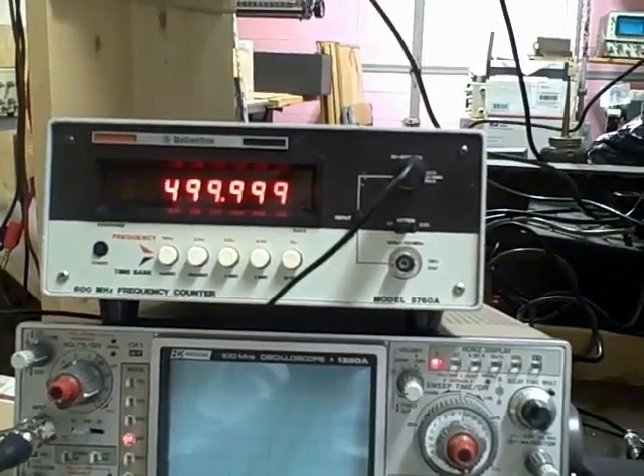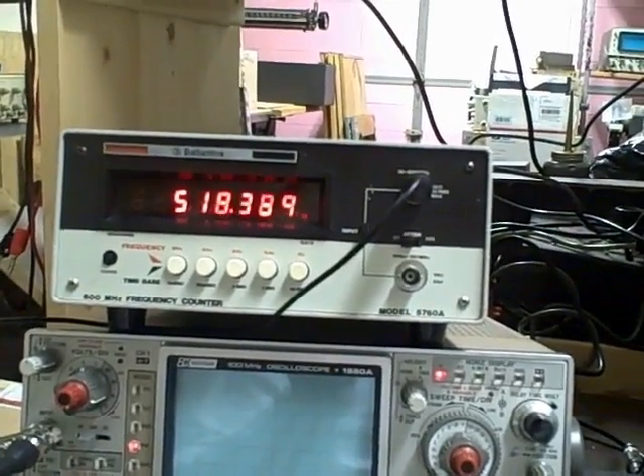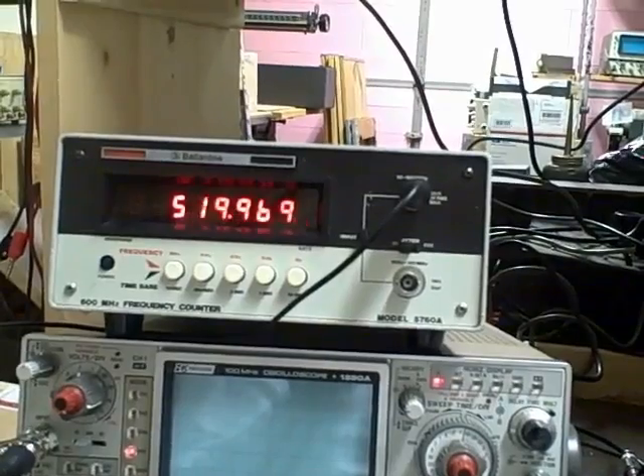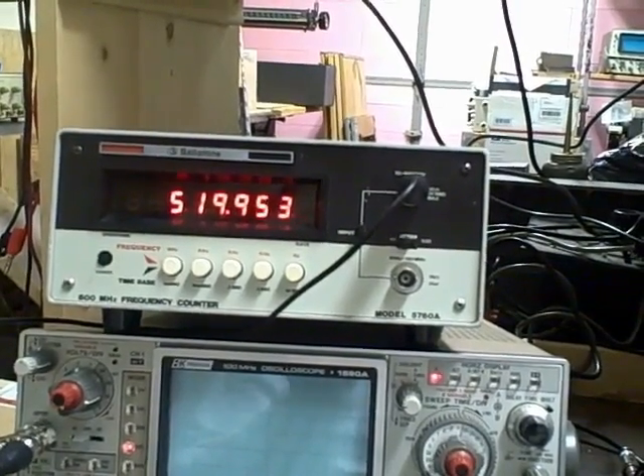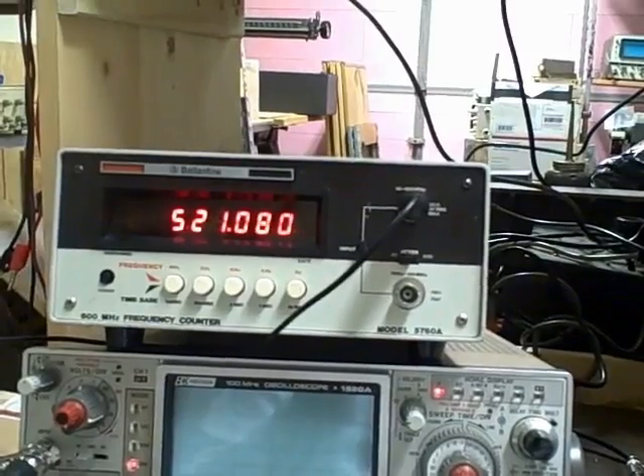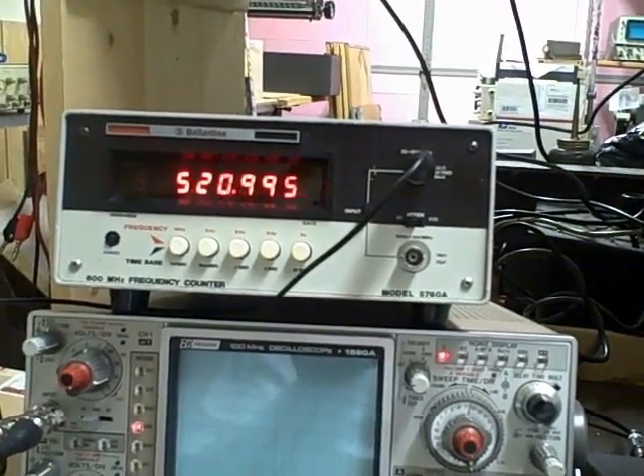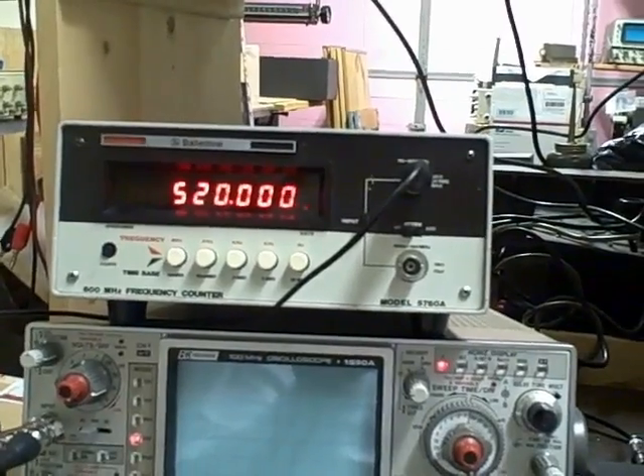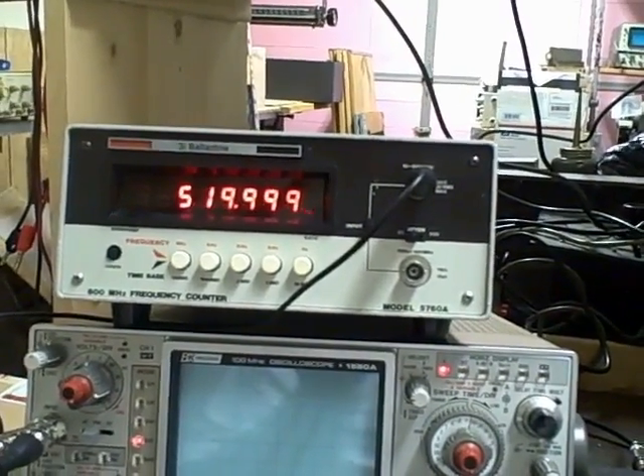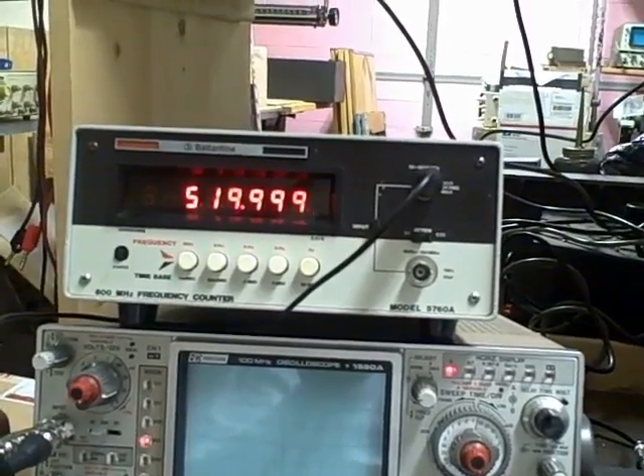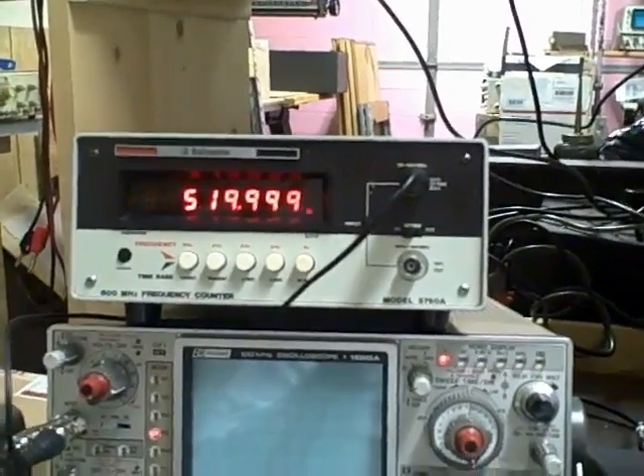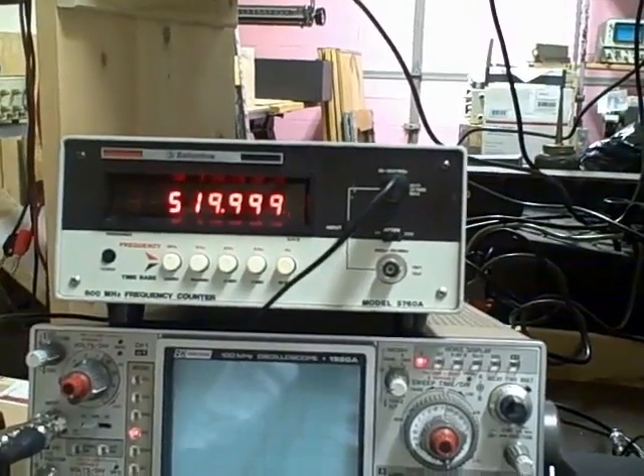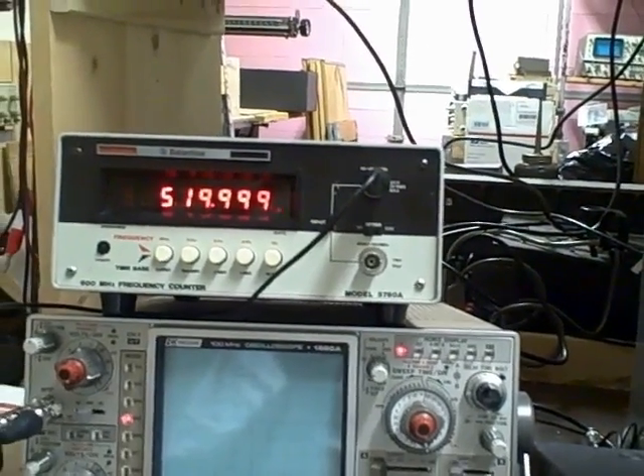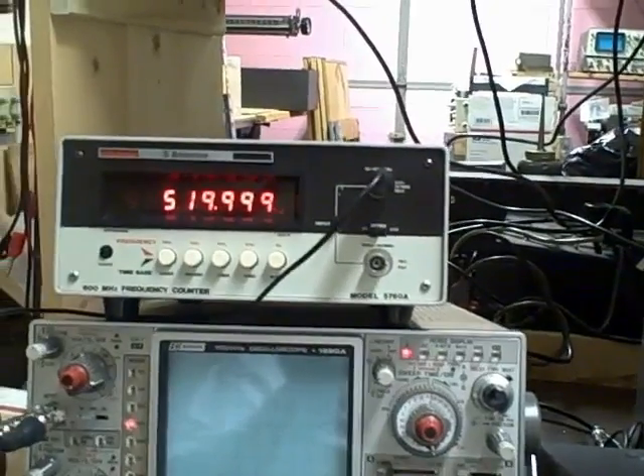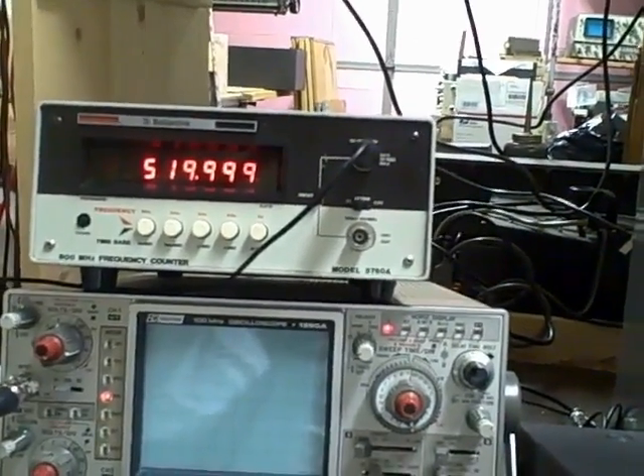And then 520 is the limit of the unit. I'll take it up to 520 right now. And I think we've latched right there. So there we are, within one least significant digit on the Ballantine, and probably it's just a matter of a touch-up on the Ballantine to get that perfect. But that's pretty dang perfect.